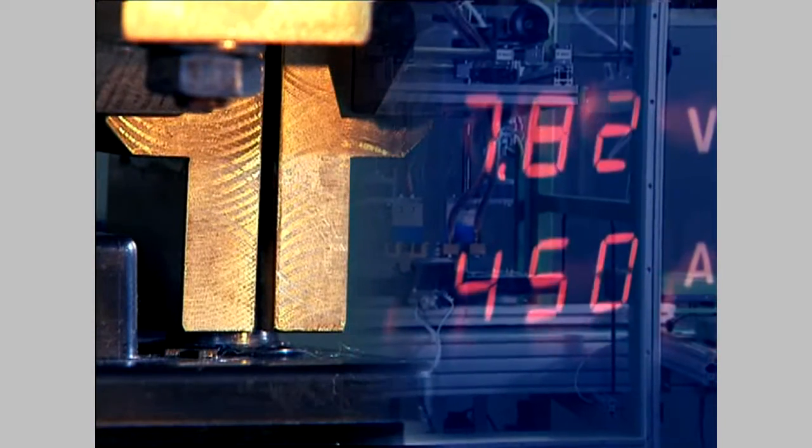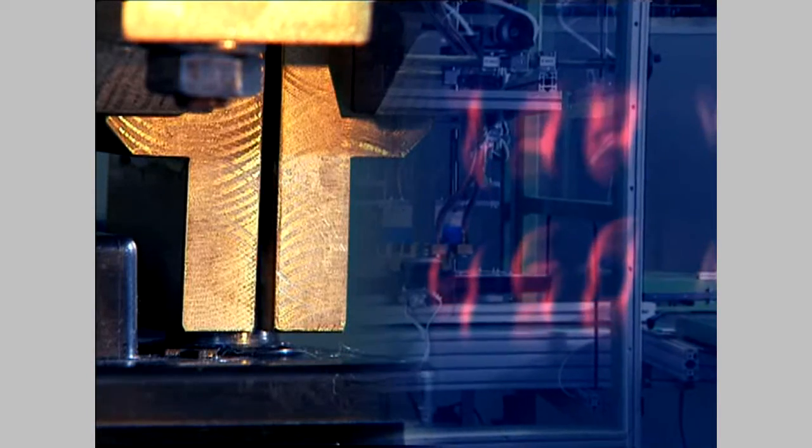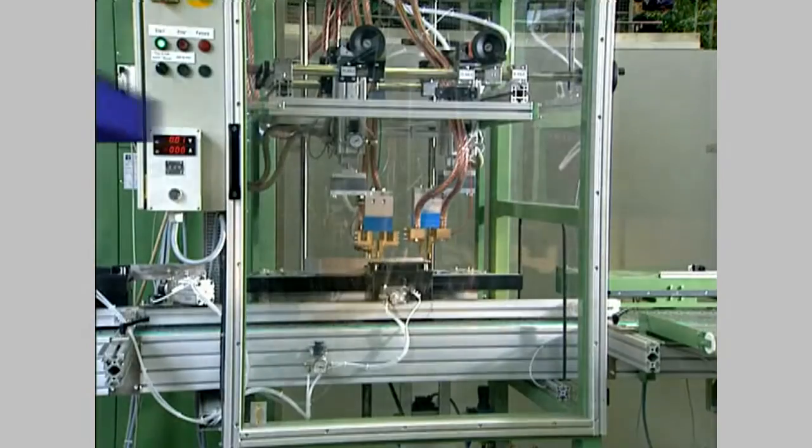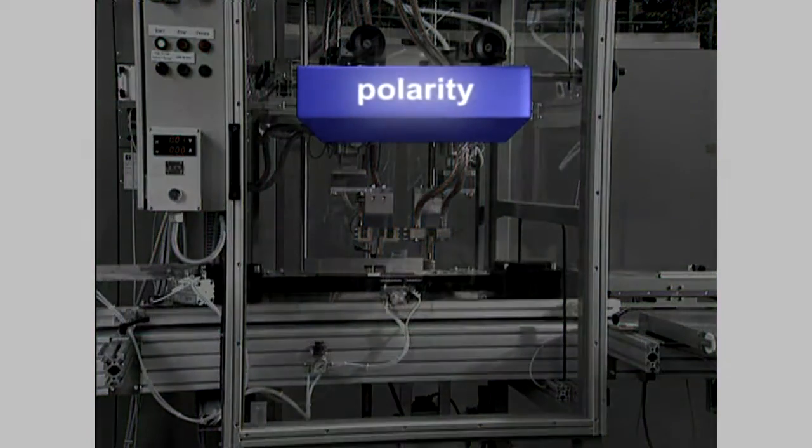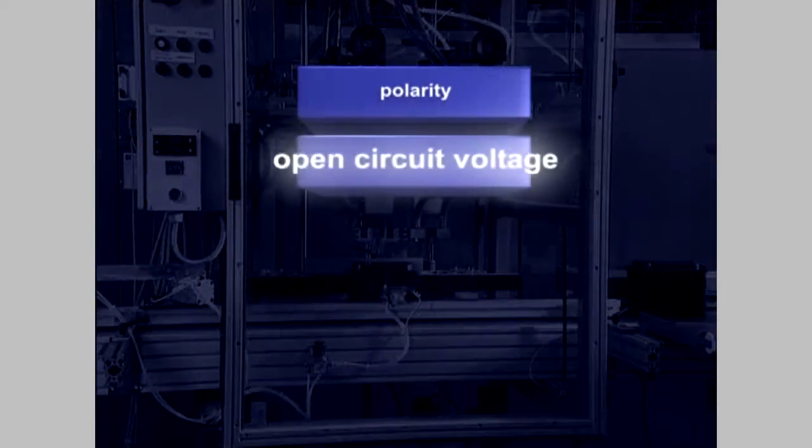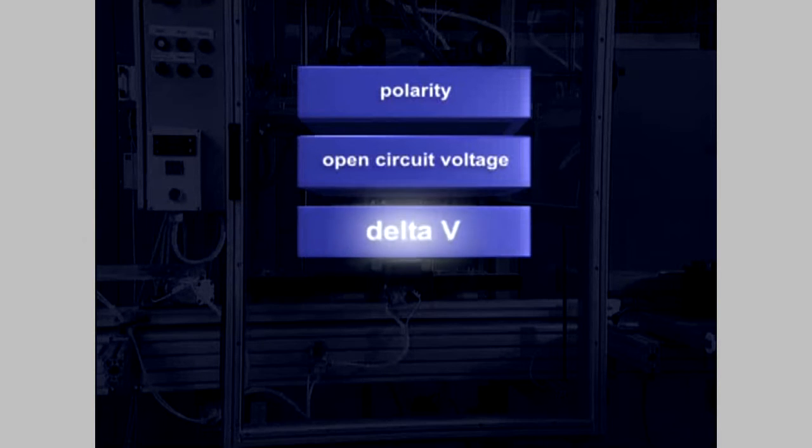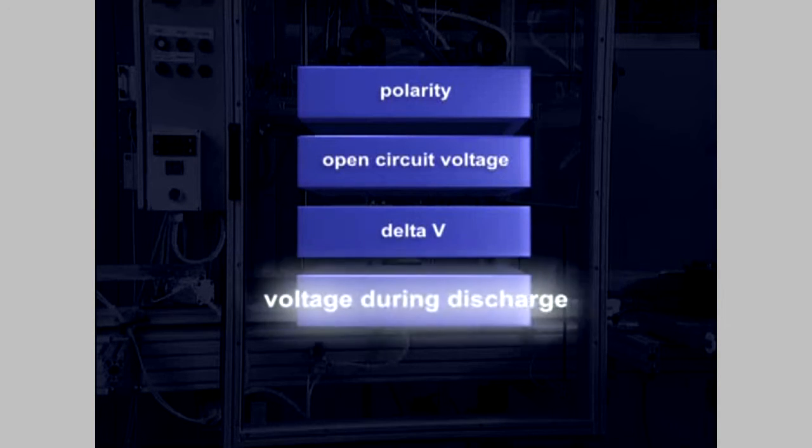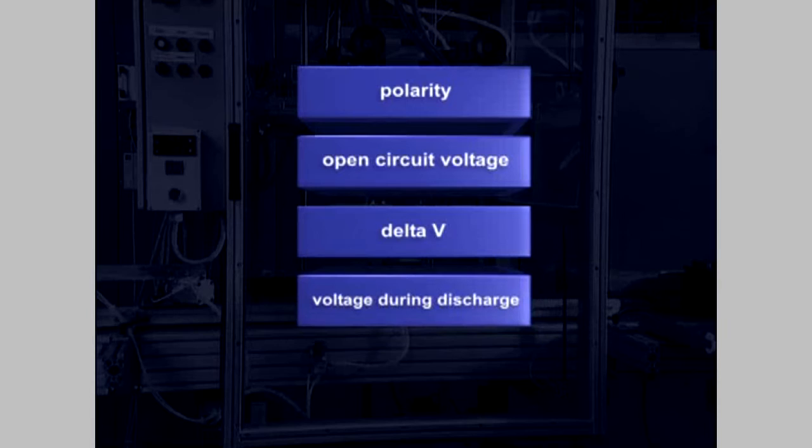To effectively avoid a variety of possible faults during battery production, each battery undergoes a test according to four criteria: polarity, open circuit voltage, delta-V evaluation, and the most significant criteria, voltage during discharge.